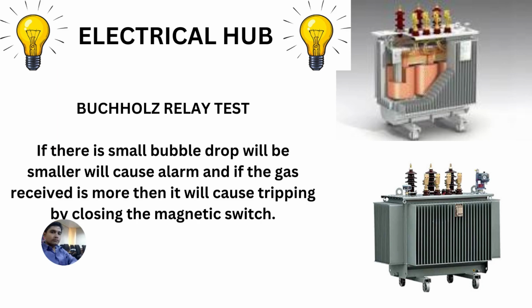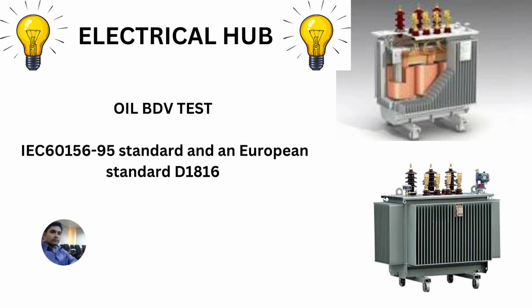So what we need to do is drain the oil and check the alarm and the tripping. If it is okay, then we can move on to the next test. The next test is the PRV test. Sorry, first the BDV test. The BDV test of the oil is done according to the IEC and the European standard. In the BDV test, we collect the oil sample from the transformer and put it in the BDV testing kit.